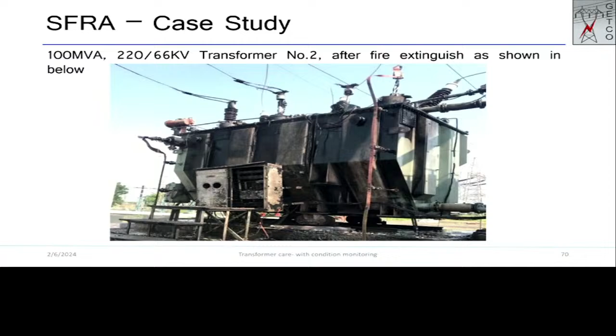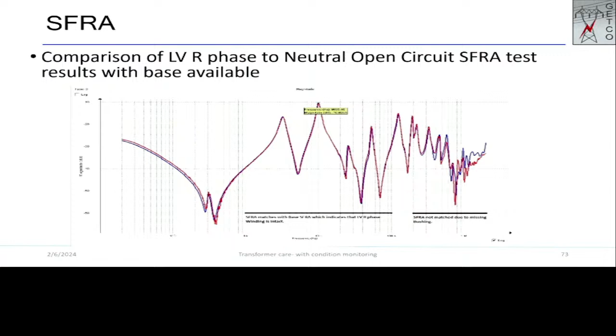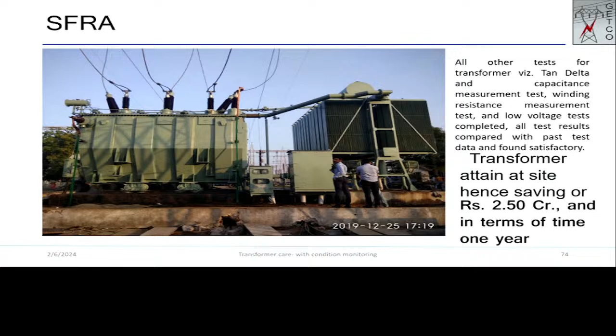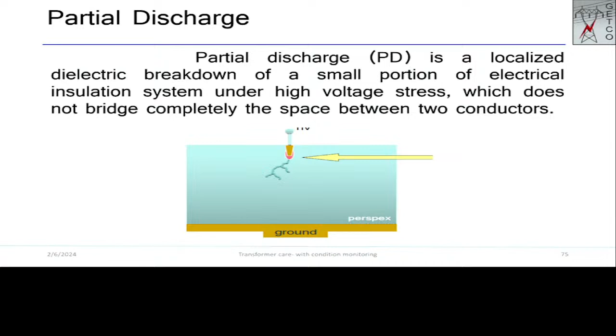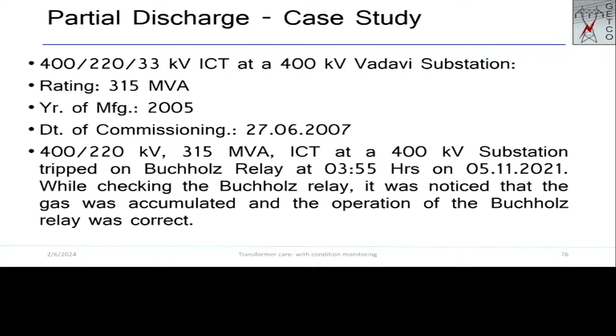In one of our substations, a transformer caught fire. Okay. So after many tries, we extinguished the fire. This is the condition of the transformer after the fire was extinguished. See the condition. Okay. So in this condition, I tested this transformer for SFRA without bushing, and compared with my base signature. In the base signature comparison, I found that there is no issue in the winding. The winding is intact. Okay. So we decided to replace all the damaged parts and put the transformer back into service. This was done within 15 days, departmentally.